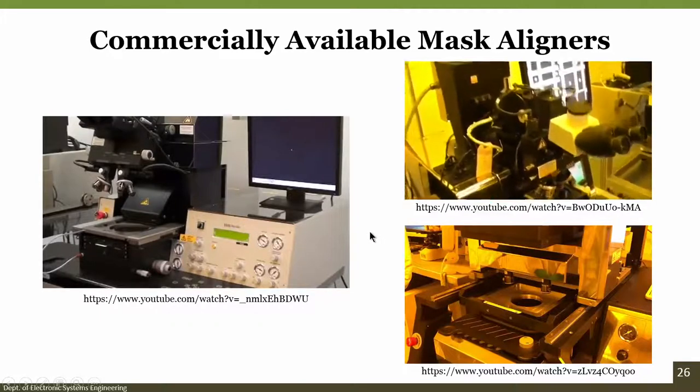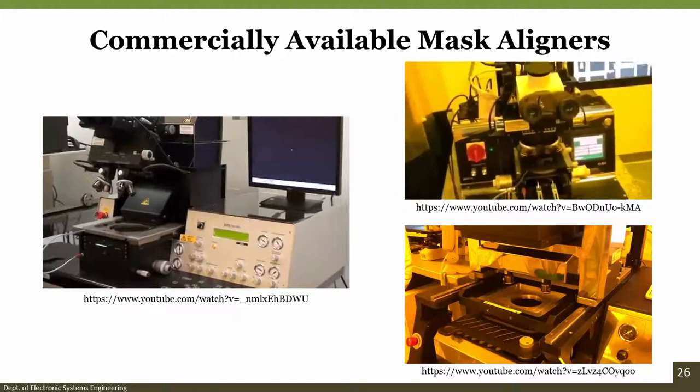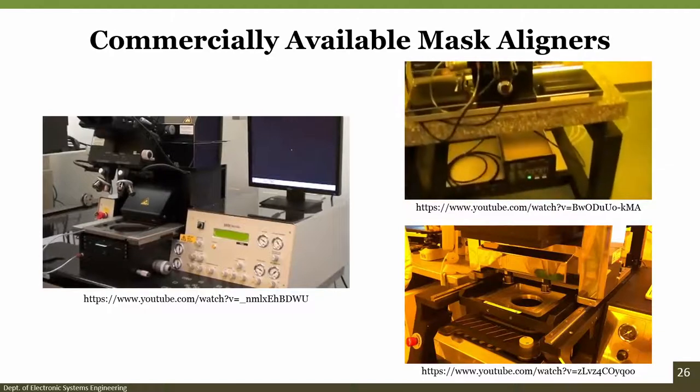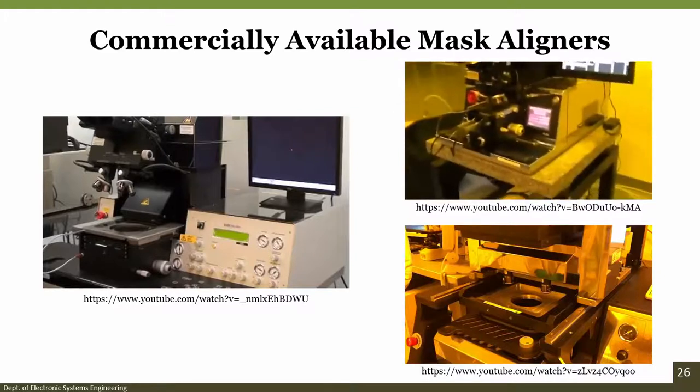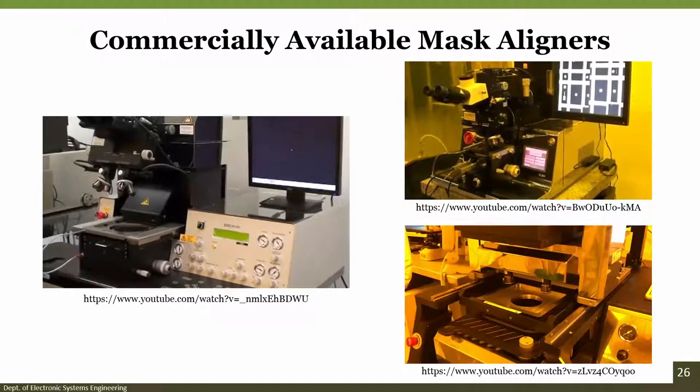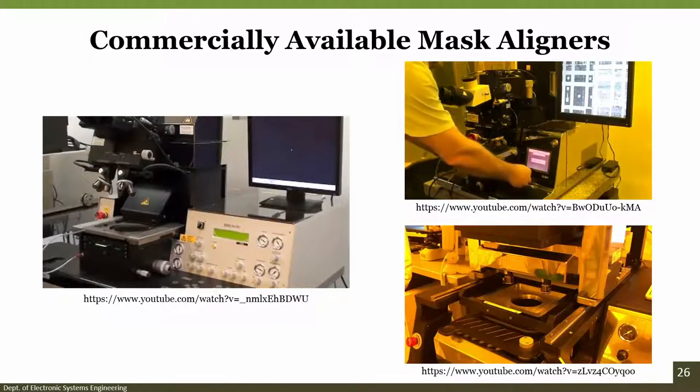Today is April 14th, 2013, and we are looking at Class 1 Equipment's MJB4, ID number 3685, serial number 191. This machine is through the refurbishment process, ready to be locked down for shipping. But first, we'll just demonstrate the operation by running a 4-inch wafer in hard contact. Contact, move to the alignment gap. This is not a matched mask and wafer, but we can at least demonstrate the alignment procedure. I'll move back to contact.